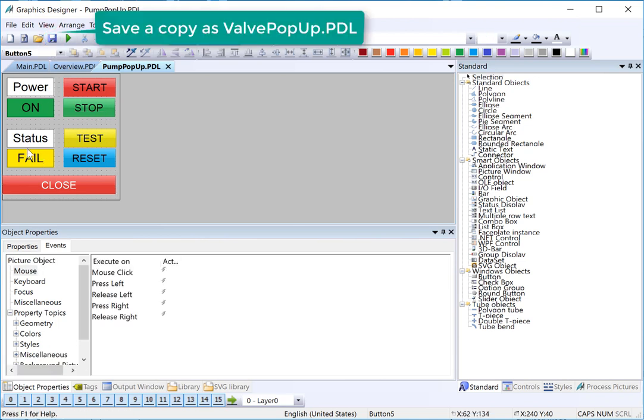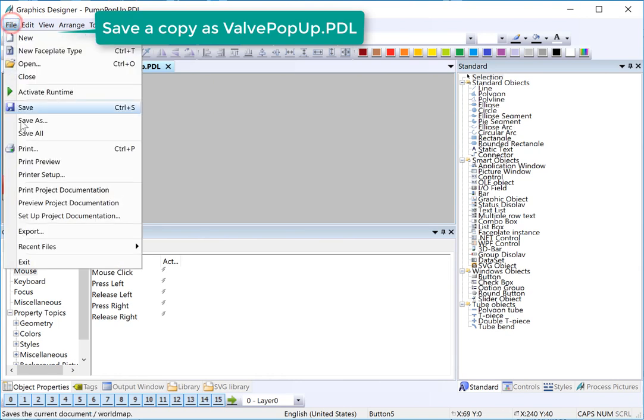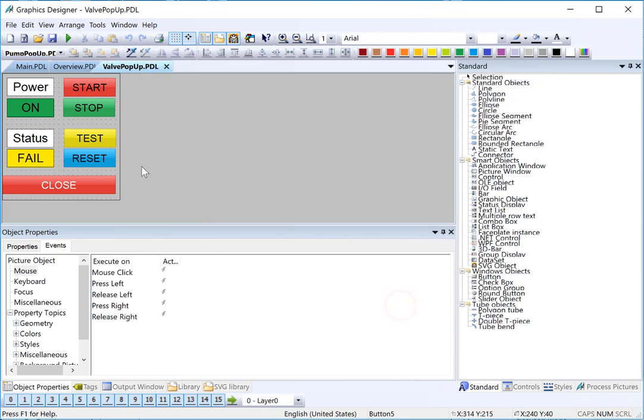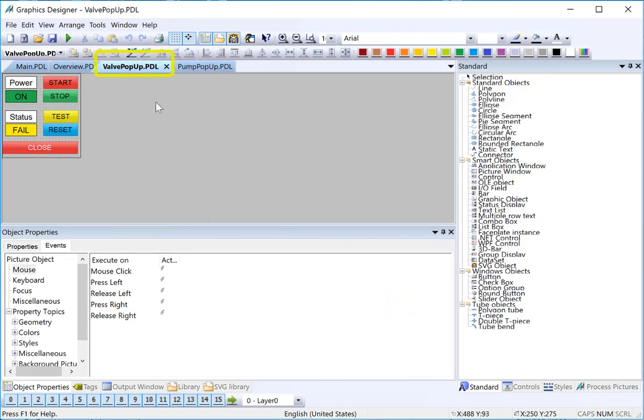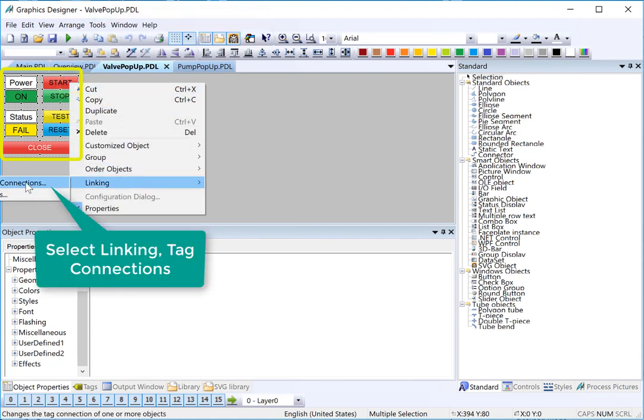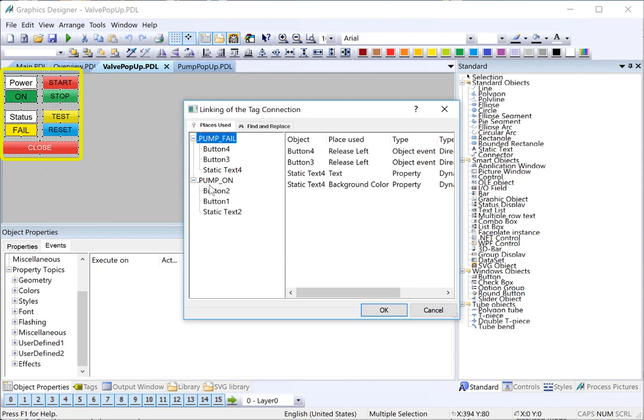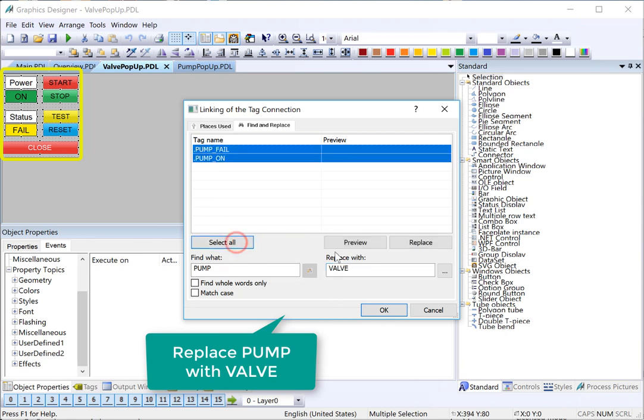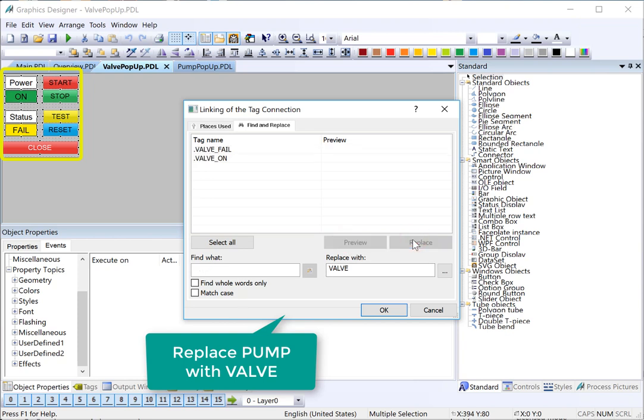Now we want to make a copy of this for the valve and then just change the appropriate texts. We'll do save as — valve pop-up. Now we need to add dynamics to our valve pop-up; we need to change all of our pump tags to valve tags, and then we have some texts that need to be changed. We can use our linking tool to do search and replace to make this go a lot faster. I'm just going to select every object on the page using Control-A, then put my cursor over one of the selected objects and choose linking tag connections. We can see all the pump-on tags, so I'll go to find and replace and just say find pump and replace it with valve. You've got to make sure you spell it right and that the case is correct.